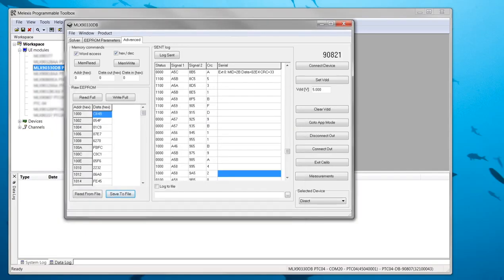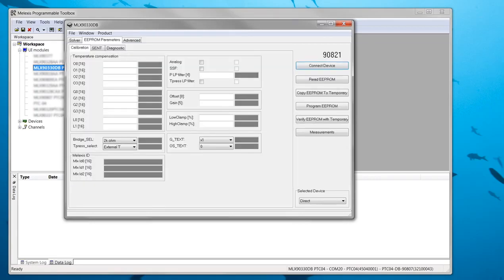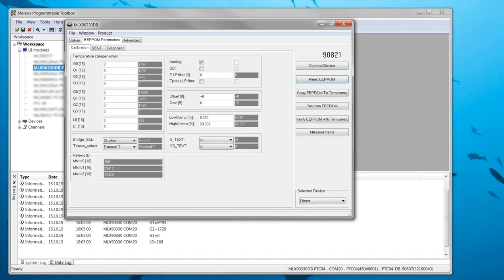To change the EEPROM configuration, I go to the EEPROM parameters tab and load in the EEPROM. This is done in 3 steps. First, press Connect the device. Then read EEPROM, and then copy EEPROM to temporary. This clears any data from a previously connected device and checks the communication. Then it reads the full E²ROM in memory of the PC. And finally, it makes a copy of the full E²ROM, which can be edited.